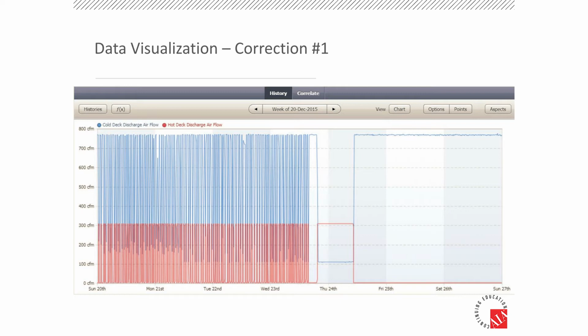Now all of a sudden our hot deck airflow has gone to zero, and our cold deck airflow is stabilized, but it's at the maximum CFM setting. So we had another meeting with them, and at this point they were asking if they could get a login to this thing, because they don't have the same capabilities of looking at the performance of their equipment.